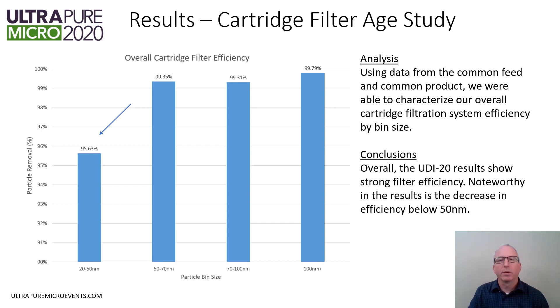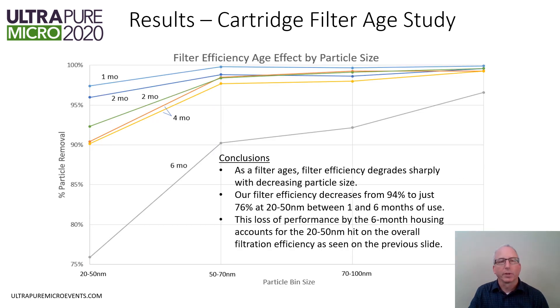Comparing the common feed and common product baselines by particle size enables us to characterize the overall filter efficiency in relation to the filter rating. Overall, these UDI-20 results show strong filter efficiency, but noteworthy is the measurable decrease in efficiency that occurs under 50 nanometers. This trend plots the filter efficiencies of each of the six filter housings as a function of particle size to highlight the effect of filter age. The one-month-old filter shows the strongest efficiencies across the full range of particle sizes, and efficiencies steadily drop as filters age from one to six months. At just six months, efficiencies at 20 to 50 nanometers plummet to just 76 percent, down from 94 percent at one month.